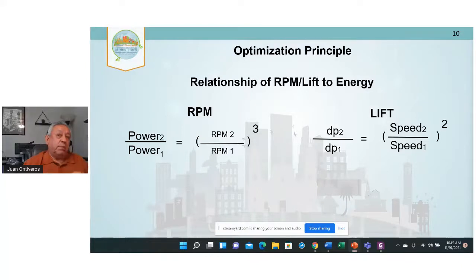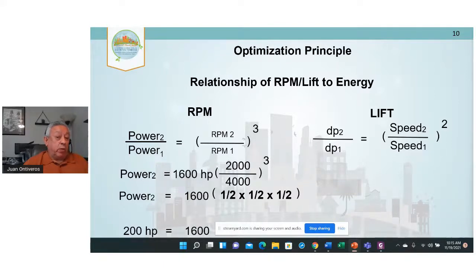There's a relationship of RPM and lift to energy, and I'll describe what lift is in a minute. The power ratio is equal to the RPM ratio, but it's cubic. And lift, the differential pressure, is related to speed squared. So bottom line, if I can reduce speed in a chiller from 4,000 to 2,000, and it's a 1,600 horsepower chiller, because it's cubic, I reduce horsepower 8 times. That's a really important principle. Instead of running chillers at full load, you want to run them at part load, because by varying the speed you get a tremendous improvement in horsepower needs.